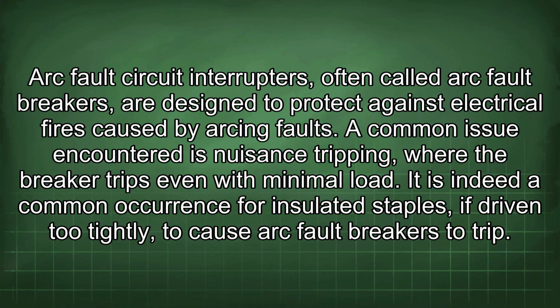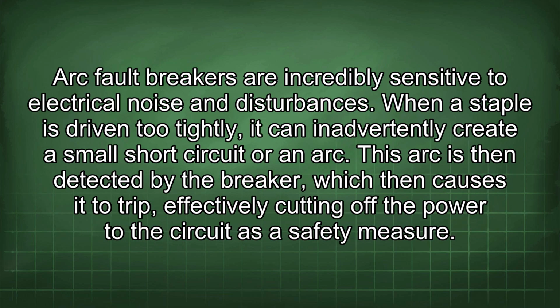Arc fault circuit interrupters, often called arc fault breakers, are designed to protect against electrical fires caused by arcing faults. A common issue encountered is nuisance tripping, where the breaker trips even with minimal load. It is indeed a common occurrence for insulated staples, if driven too tightly, to cause arc fault breakers to trip. Arc fault breakers are incredibly sensitive to electrical noise and disturbances.